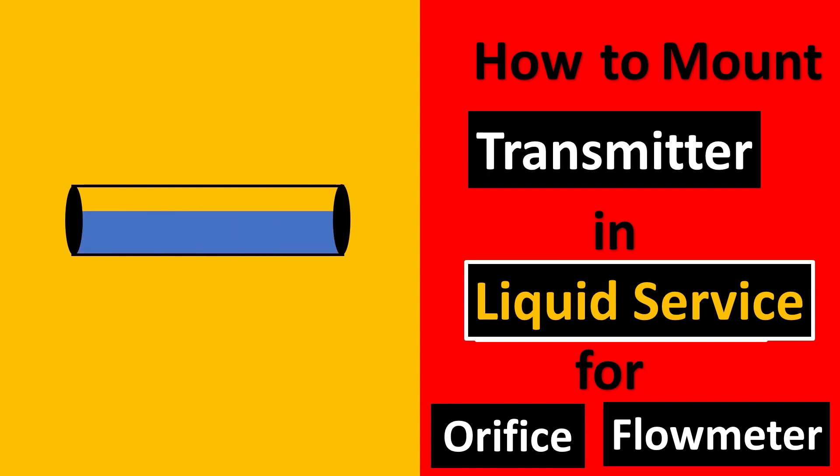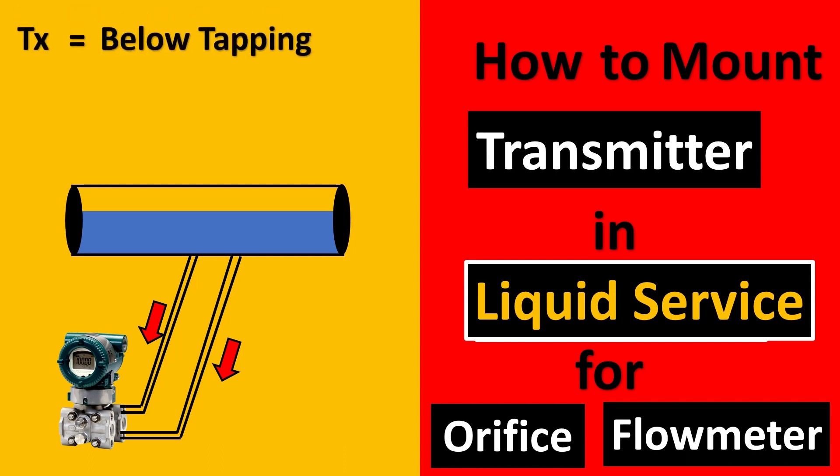Now the next question is what do you do in liquid services? In liquid services, the transmitter would be below the tapping and the slope. Remember that the slope will always be towards the transmitter and not towards the pipe.